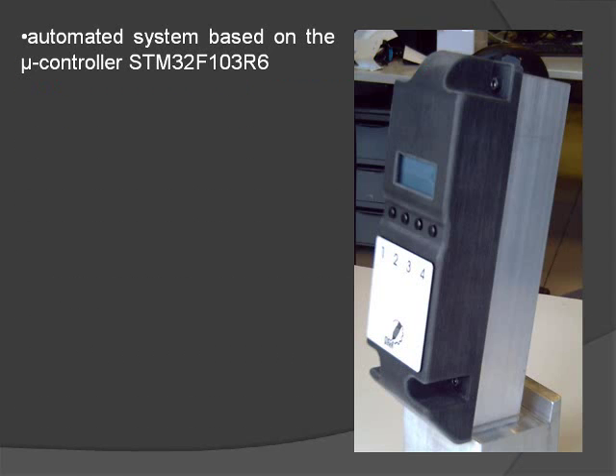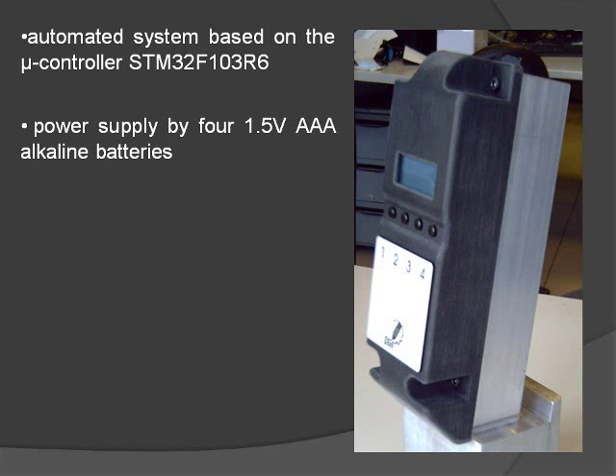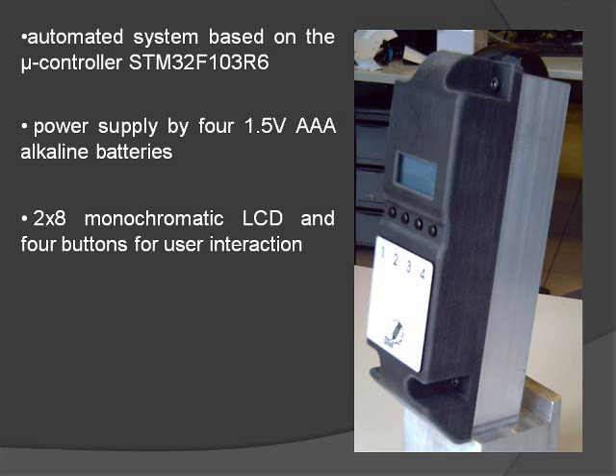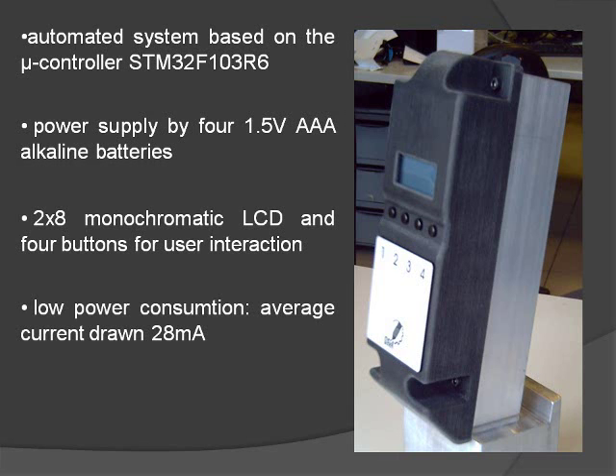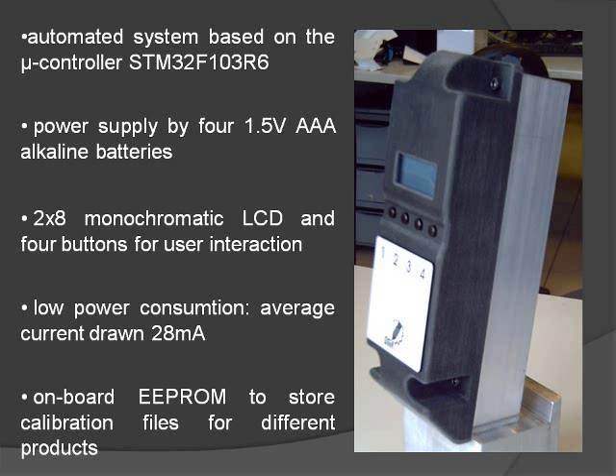The proposed instrument features an electronic board, based on the STM32 microcontroller by ST Microelectronics. Its power supply is provided by four 1.5-volt alkaline batteries. The system features 4 buttons for user interaction and a liquid crystal display with 2 lines of 8 characters each to display measurement data. The power consumption is low. The average current drawn is 28 mA if the display backlight is turned off. A non-volatile EEPROM memory is present on the designed electronic board to allow the user to store the calibration parameters for better accuracy in the measurement of oil concentration.